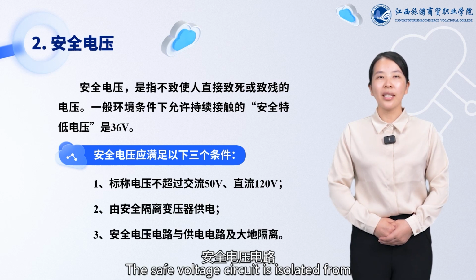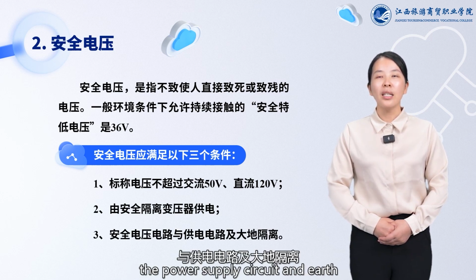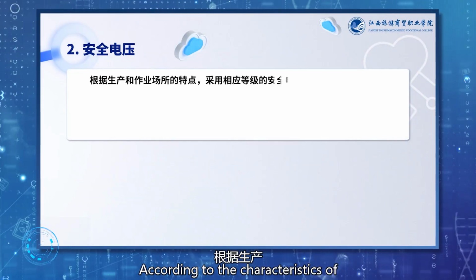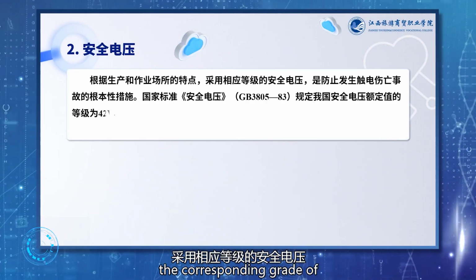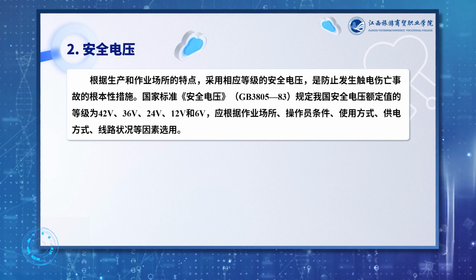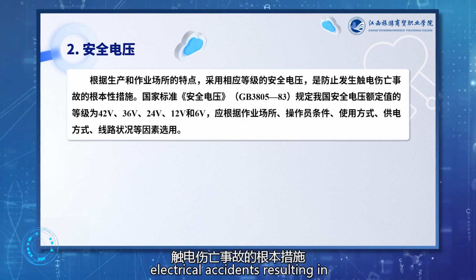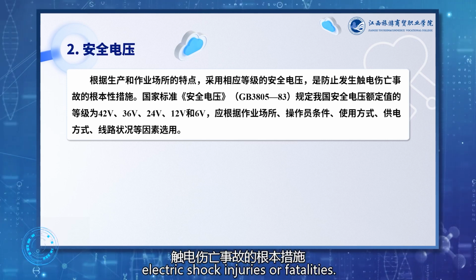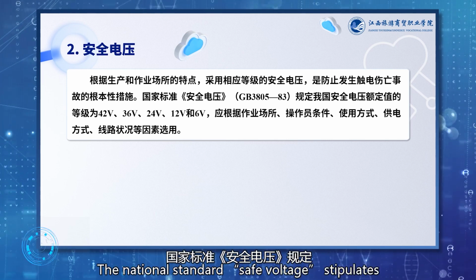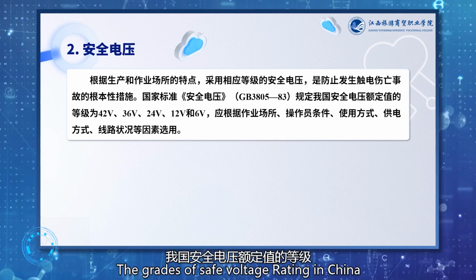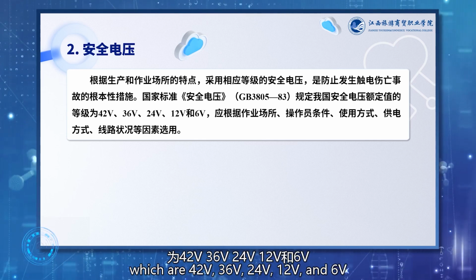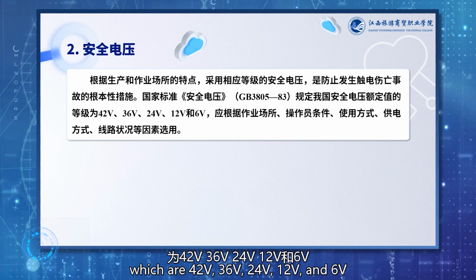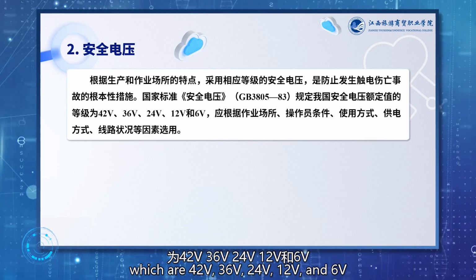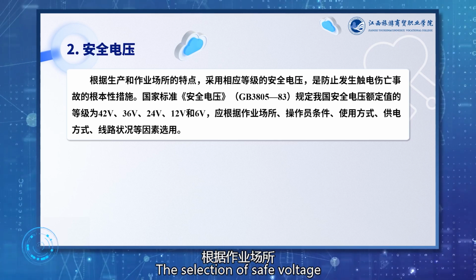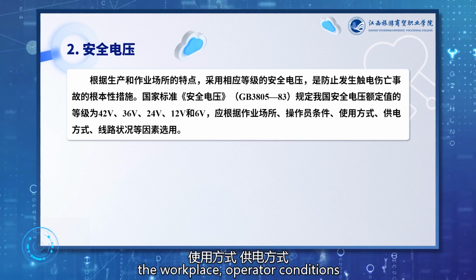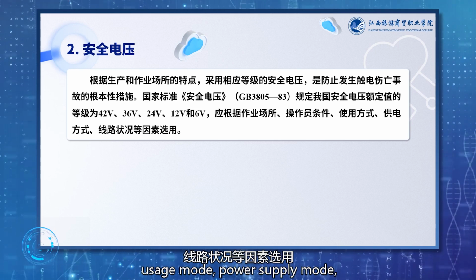The safe voltage circuit is isolated from the power supply circuit and earth. According to the characteristics of the production and workplace, the corresponding grade of safe voltage should be adopted. This is the fundamental measure to prevent electrical accidents resulting in electric shock injuries or fatalities. The national standard safe voltage stipulates the grades of safe voltage rating in China, which are 42V, 36V, 24V, 12V, and 6V. The selection of safe voltage depends on factors such as the workplace, operator conditions, usage mode, power supply mode, and line conditions.